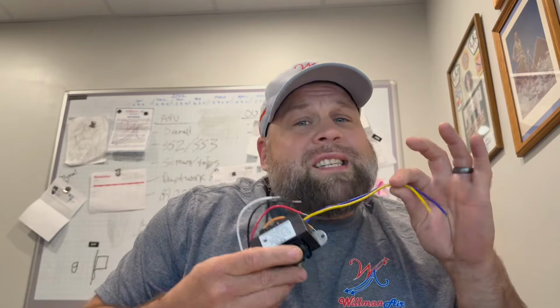By the way, this is a transformer. It goes in your air handler, in the top compartment where the heater and all the electrical connections are done. It basically steps down your high voltage, 240 on an air handler, to 24 volts. That 24 volts is then used to power your thermostat and used as control signals.